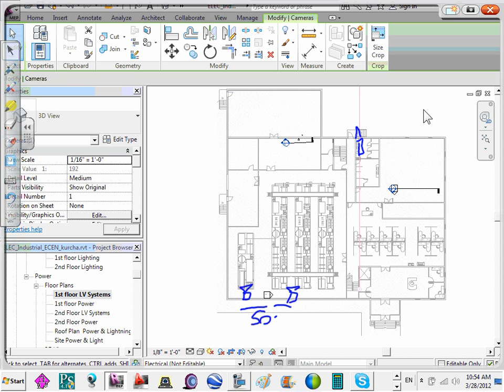Now, hazardous area here. Do you know if this is Class 1 Div 1, Class 1 Div 2, explosion proof? They do make explosion proof horns and explosion proof strobes, but they're going to be separate. They do not make combination devices. So depending on which level you need, there's hazardous location and there's explosion proof. It all depends on what group you're looking at. Let's see here. And the data center, we'll pretty much have everything covered. You're going to have your fire alarm panel up in here.